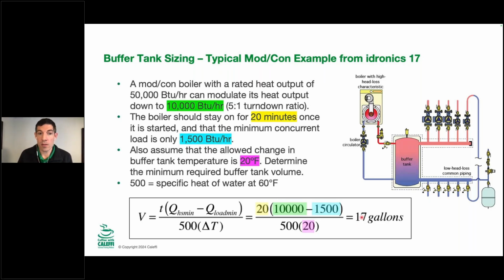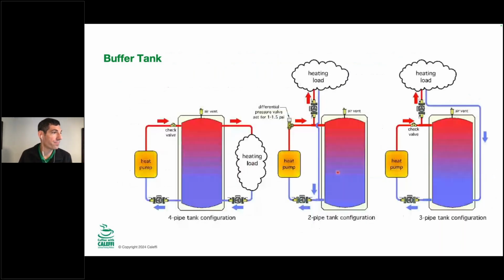Don't even know where you'd find one of those, but just to illustrate that with a ModCon or something that has even a 2-to-1 turn down ratio, it really takes the size of the buffer tank down, and you won't need as much as you may assume if you thought that it always had to be 119 gallons or 60 gallons or something like that. That's the formula with the ModCon to figure out, or anything that modulates, that you can find the minimum turn down ratio or equivalent with a heat pump. That's how we're going to size a buffer tank.